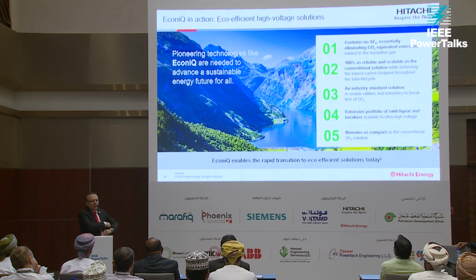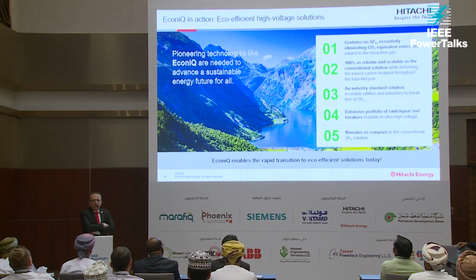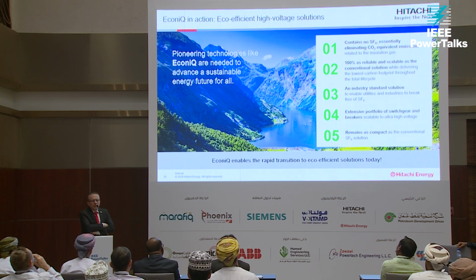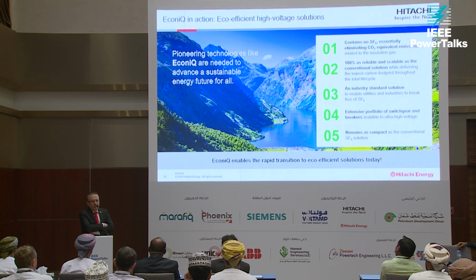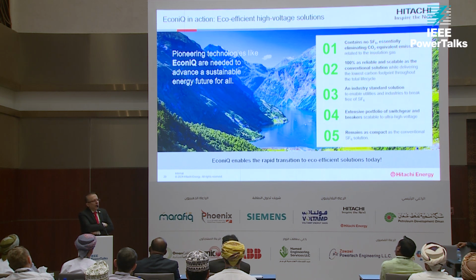Then how do we build this EconiQ solution? We have a long history and experience with SF6, so we said, let's build on the same SF6 technology - we know the interruption technology. Let's introduce a gas with more or less the same characteristics as SF6: non-toxic, ozone friendly, good dielectric characteristics, usable for arc extinguishing, low boiling point, and not flammable. With all these requirements, we came up with a gas mixture we can use for insulation.